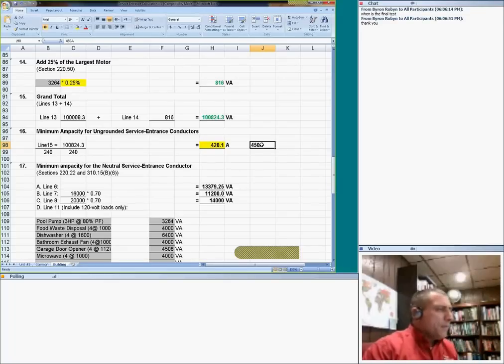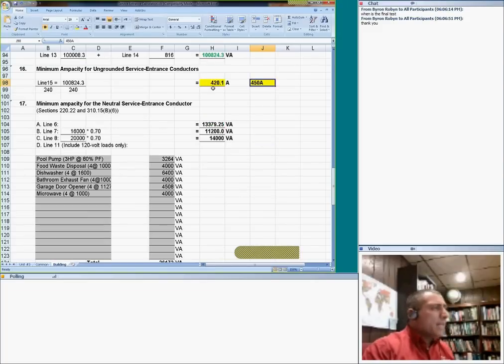So you can have a 450 amp fuse, and then feed a 600 amp panel from it, or a 500 amp panel. Question, guys. So here, I came up with the size of my service, 450 amp for this quad. Some of you guys who do residential might think, well, that's too much, yeah. But remember, they have dryers and ranges and a swimming pool in this apartment building. A lot of stuff. And then how to calculate the service. So that's service. And then you do the neutral.